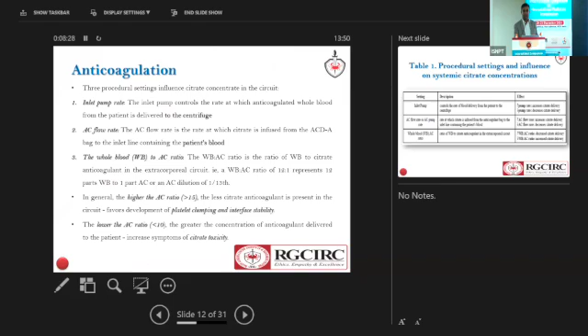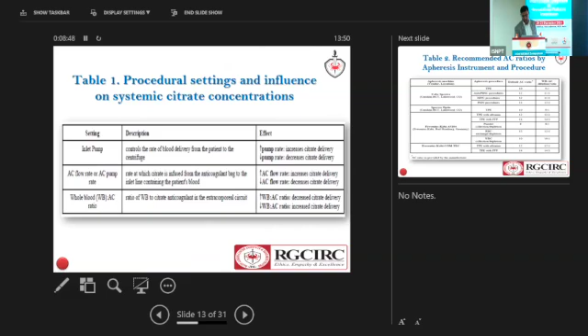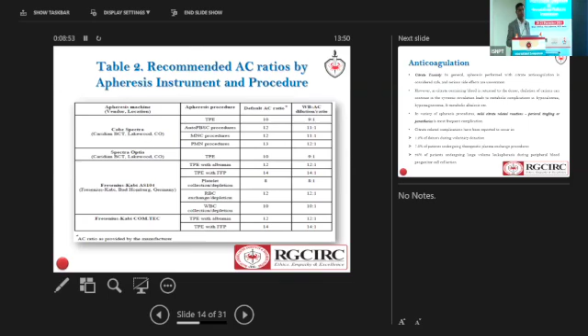It is the AC ratio. Most of the instruments fix the AC ratio at 12:1, meaning we are taking 12 parts of whole blood and 1 part of the anticoagulant. So the higher the AC ratio, there are chances of clotting or clumping, and the lower the AC ratio, the more delivery of the ACD there is, so more citrate toxicity will be there. So the inlet and AC flow are proportional to the delivery of the ACD, and the whole blood to AC ratio is inversely proportional to delivery of the citrate. So as I said earlier, most instruments fix their AC ratio at 12:1.